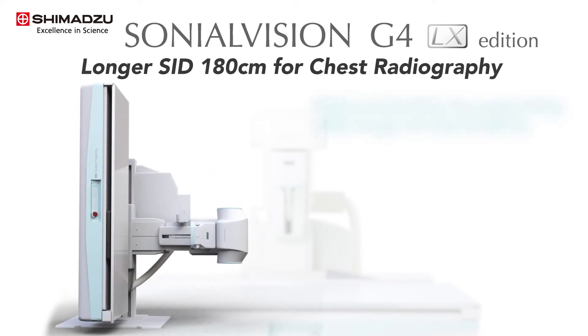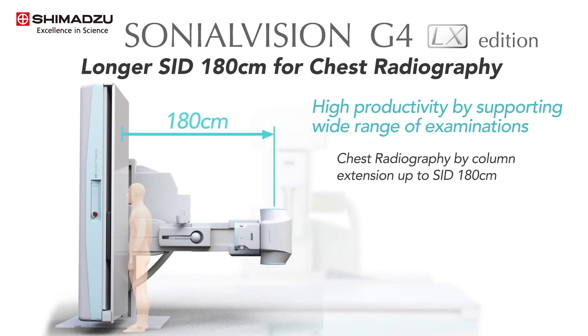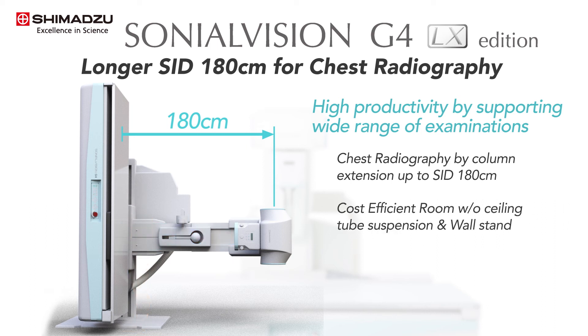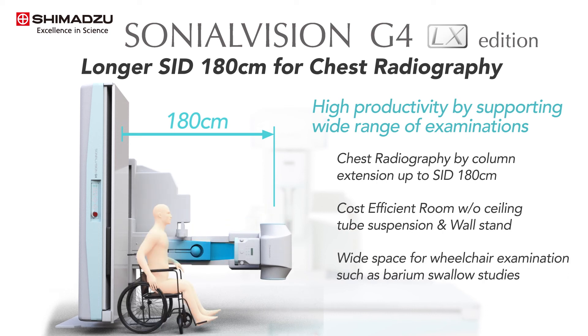With the 180 centimeter SID configuration, the SONIALVISION G4 LX brings additional functionality for performing chest exposures with the table in the vertical position. For rooms that do not have space to add a ceiling tube suspension and wall stand, the 180 centimeter SID is used for performing chest X-ray exposures. Furthermore, the wide space provides comfort for patients during wheelchair examinations such as barium swallow studies.